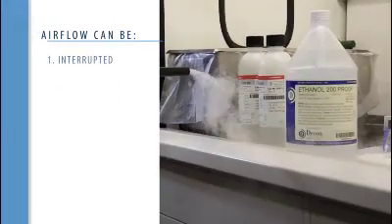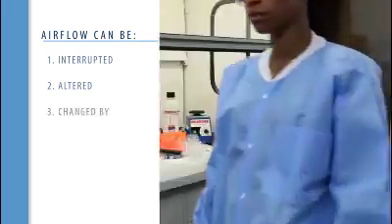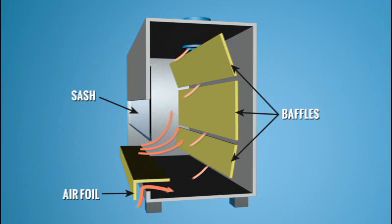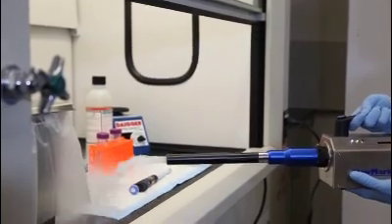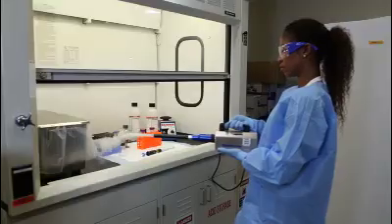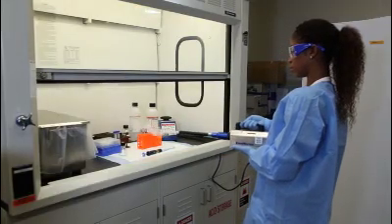Airflow in a chemical fume hood can be interrupted, altered, and changed by different factors. Air flows into the hood capturing and containing contaminants, preventing them from escaping into the laboratory room. The smoke shown here provides visual demonstration of how air flows in a fume hood.